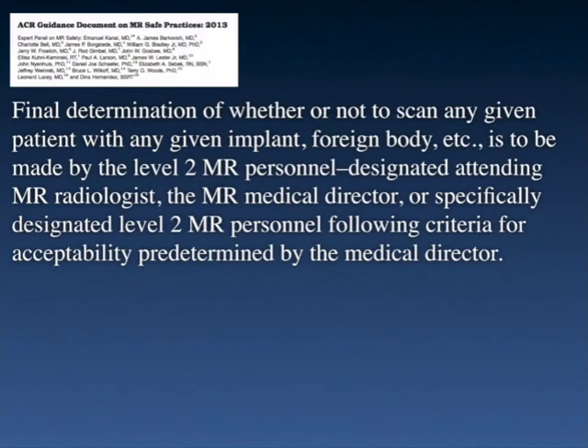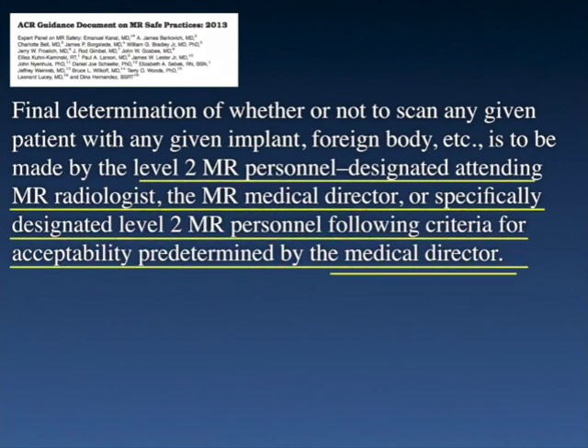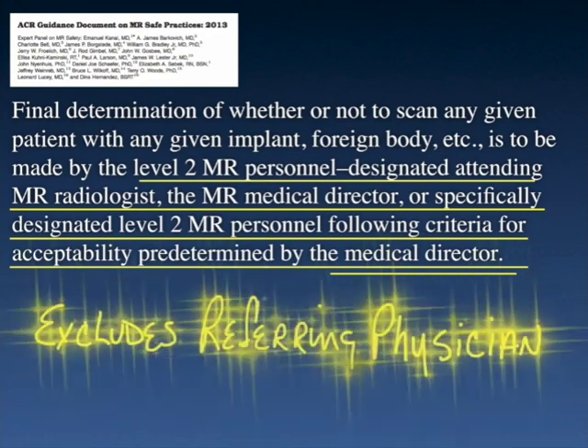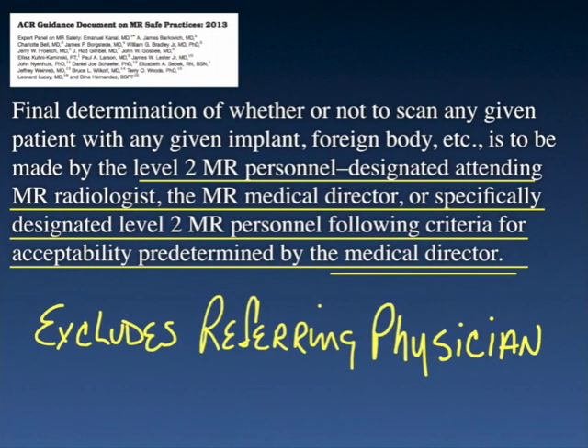The ACR guidance document states that the final determination of whether or not to scan any given patient with any given implant or foreign body is to be made by the level 2 MR personnel designated attending MR radiologist, MR medical director, or specifically designated level 2 MR personnel following predetermined criteria for acceptability set by the medical director. This clearly excludes the referring physician, implanting surgeon, the physician's nurse, or a relative — these people are not reliable sources for accurate MR safety information relative to implants or devices.